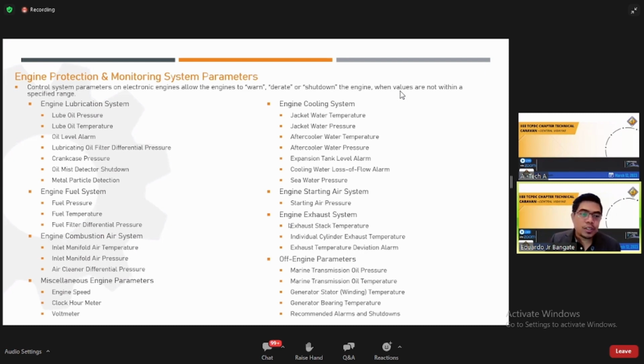Okay, sa engine lubrication system: lube oil pressure, lube oil temperature, oil level alarm, lubricating oil filter differential pressure. What is this? Lubricating oil pressure, oil filter differential pressure. It means that there are sensors that monitor if the filters of our generators are blocked. There is a sensor in the inlet and there's another sensor in the outlet. The difference between these two sensors will tell you whether or not your filter is blocked. Okay? So crankcase pressure in the engine.